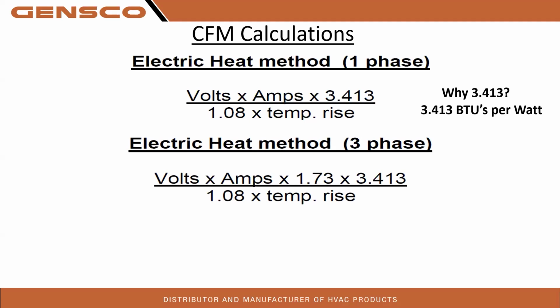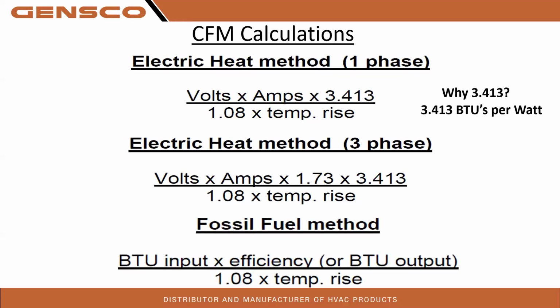So electric heat method with 3-phase is going to be the volts times amps times 1.73 times the 3.413. So you're still going to divide that by your temp rise, your delta T, times 1.08. And that math works out pretty good. That gets you pretty close to your CFMs.